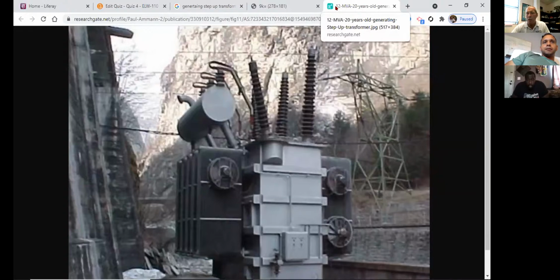There we go, open image in new tab. So does anybody see up here at the top, what size transformer is this? 12 megavolt. There you go, excellent, 12 MVA. So at my substation, I've got a 12 million volt amperage. So really, how many watts is that in our terms? If kVA, if 50 kVA equals 50,000 watts, what's a 12 MVA? 12 million watts. 12 million watts output on this transformer, okay? So, and that's for layman terms. Of course, I told you before, an engineer is going to dispute that because you've not factored out many other things. What do they have on both sides?